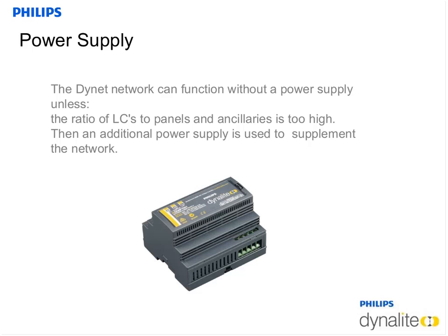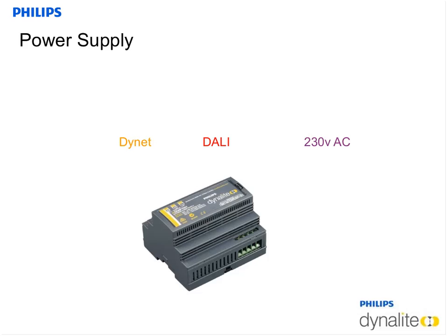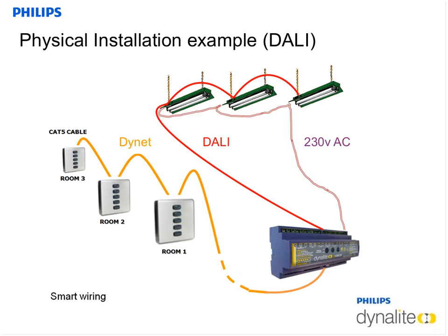It's only when we start dealing with high drain devices, for example, touchpads, which might drain, say, an amp of power. So there are calculations available. There is a template available for the designer to calculate when we need to include our power supply. So this is different from a lot of the competition. Again, I mentioned KNX because you have to calculate power supplies throughout the whole network as a prerequisite.